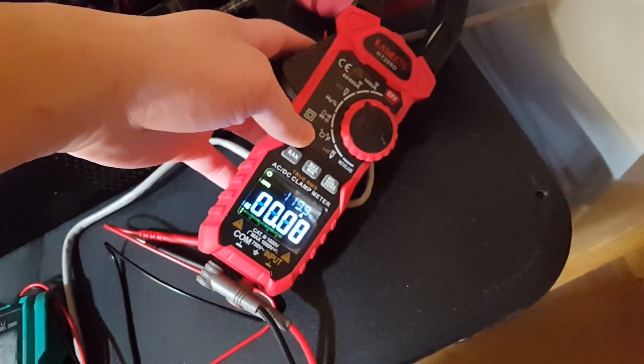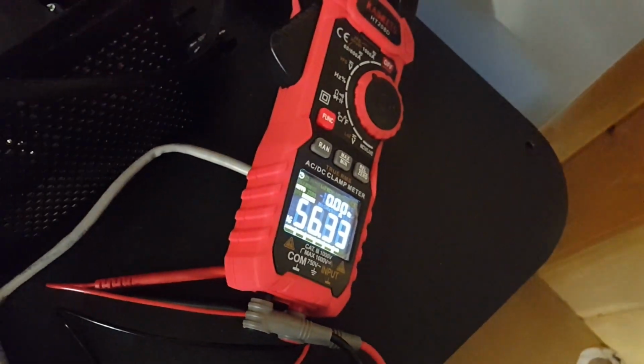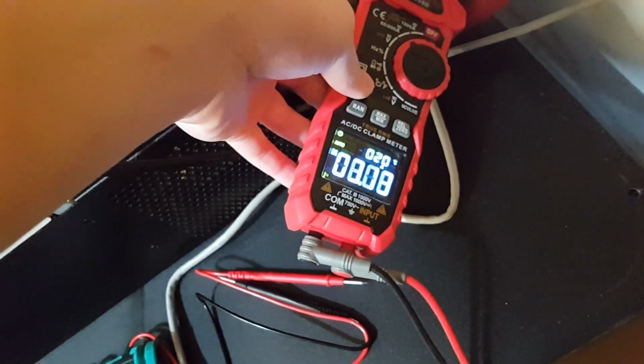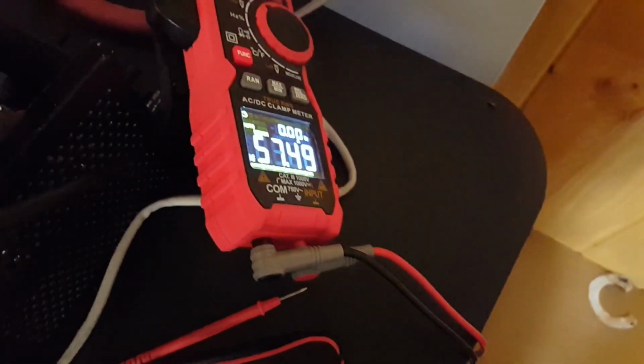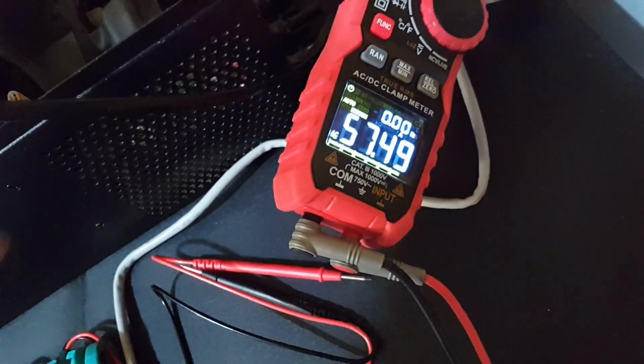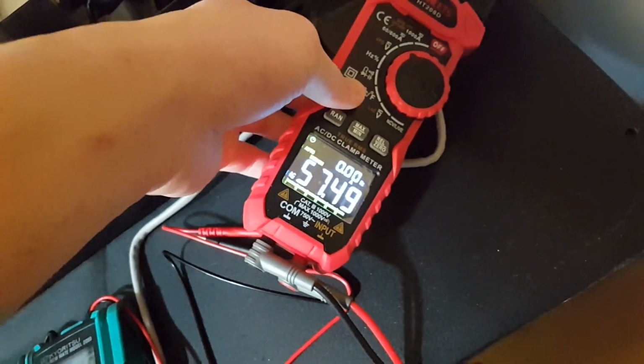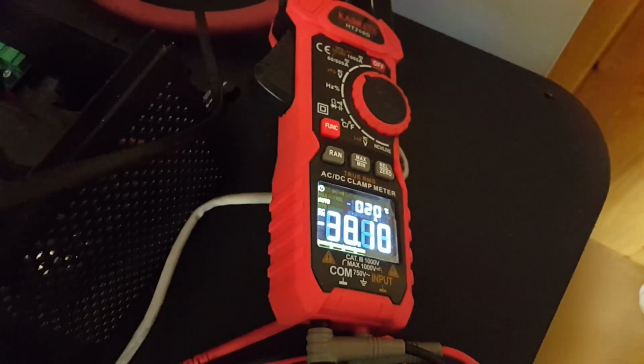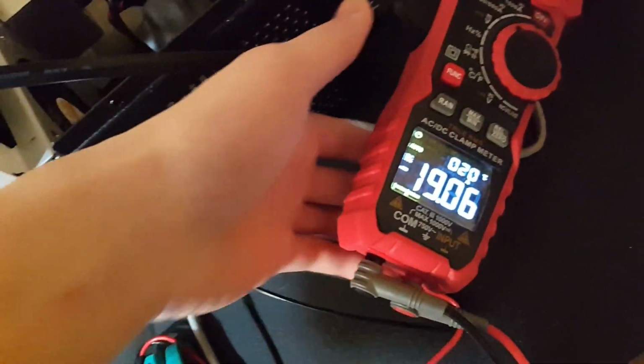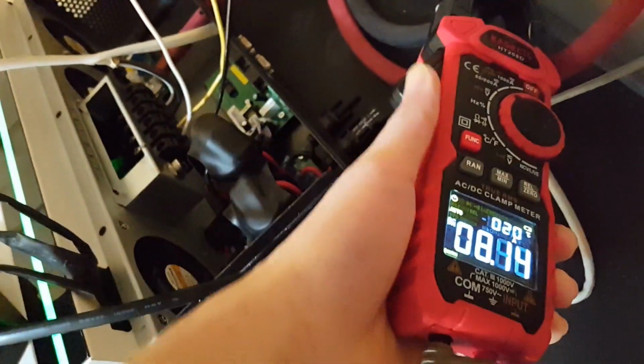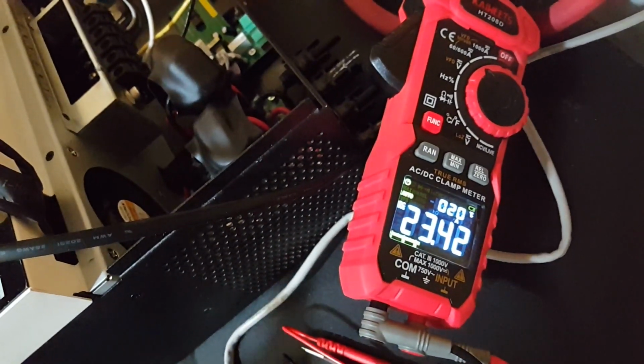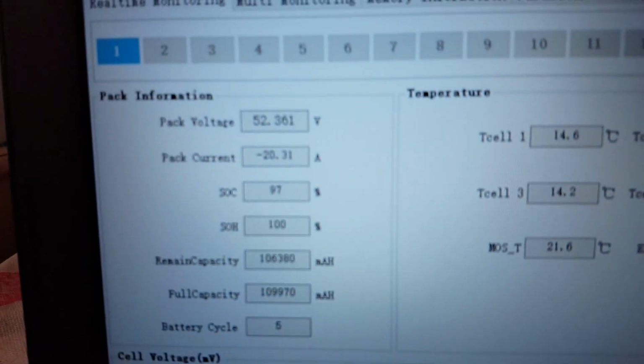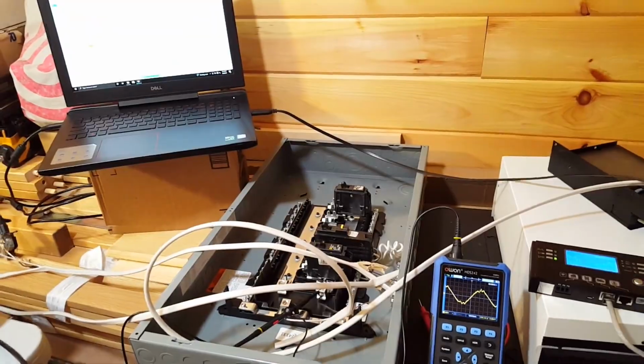Let's check inrush for the battery. 56 on one cable. Let's test with the other cable, see if there's any difference. 57. Alright, so pretty close. Let's check running amps on the DC side. 19 on one cable. 23 on the second cable. BMS firmware says we're discharging at 20 amps. Okay, so that test was for the shop vac.